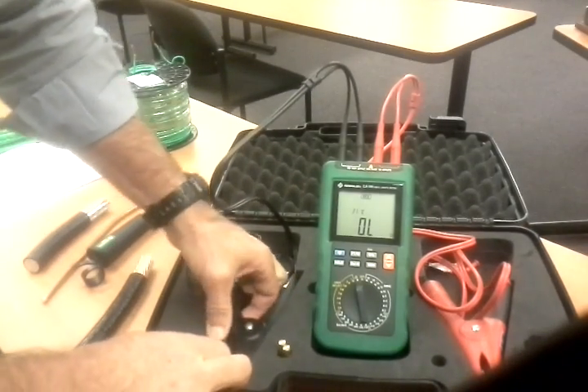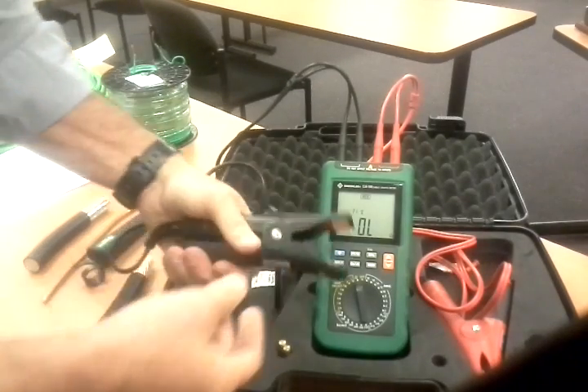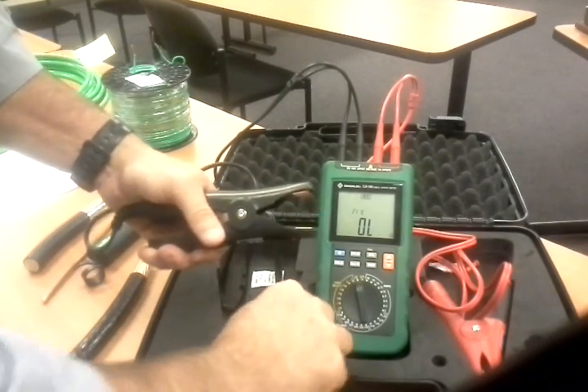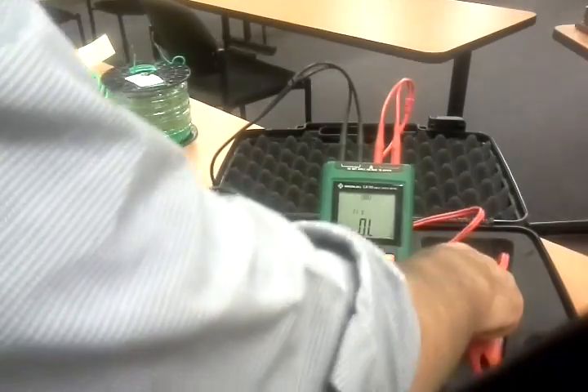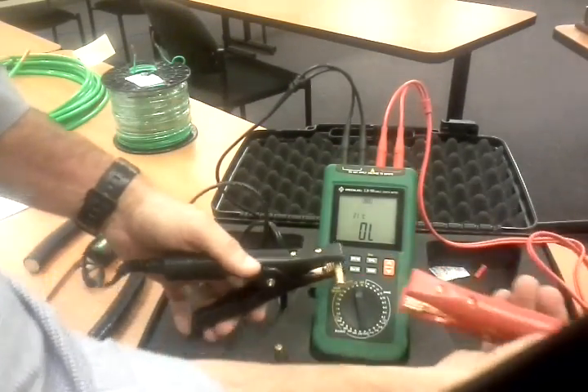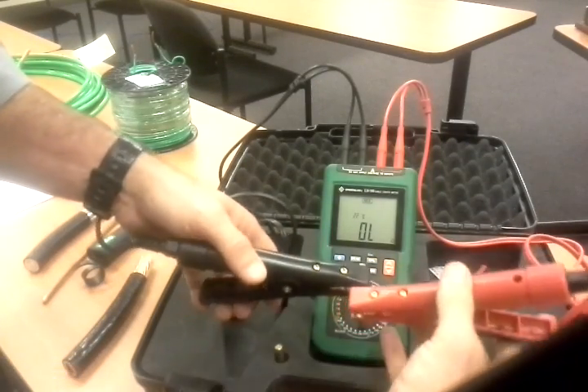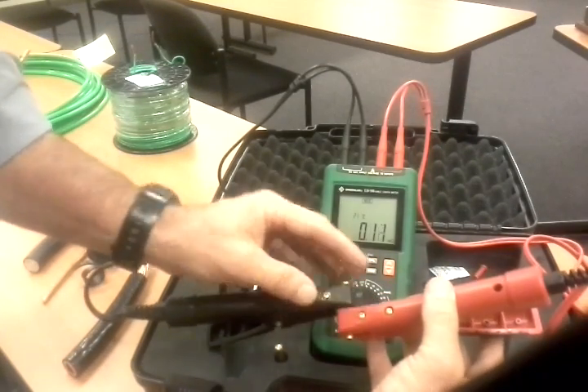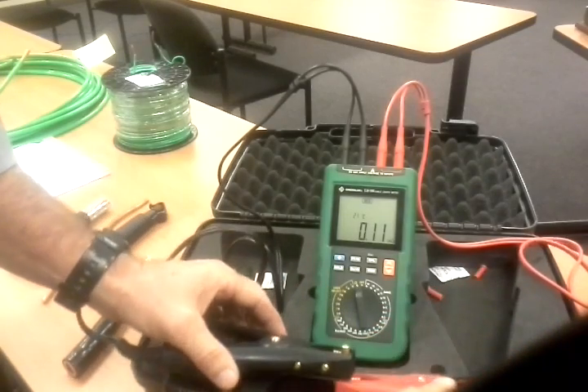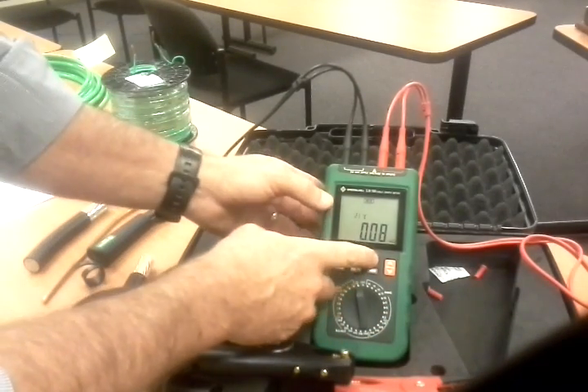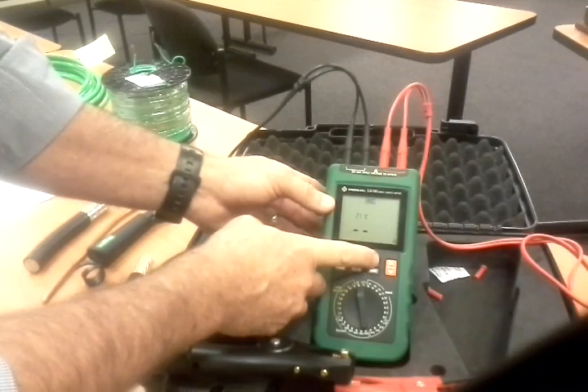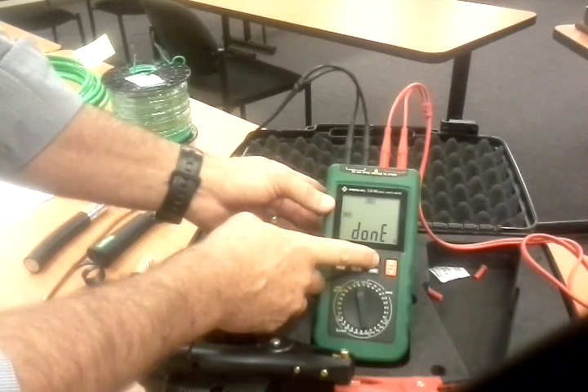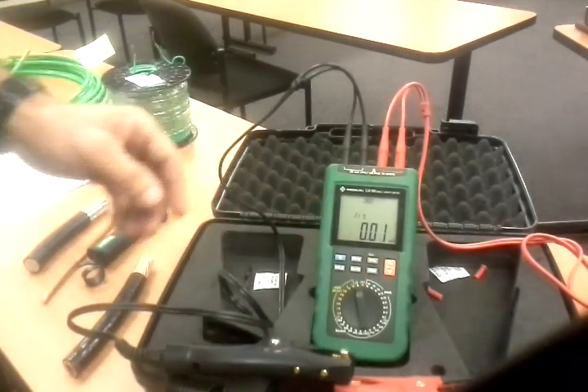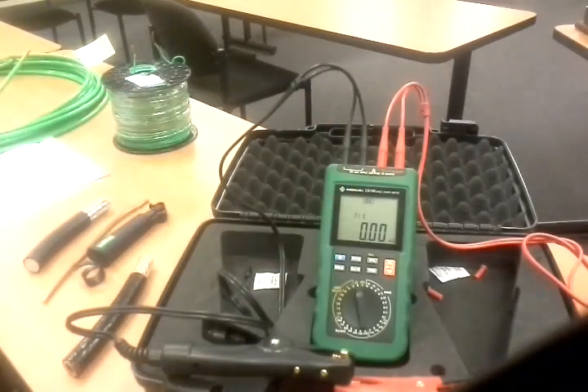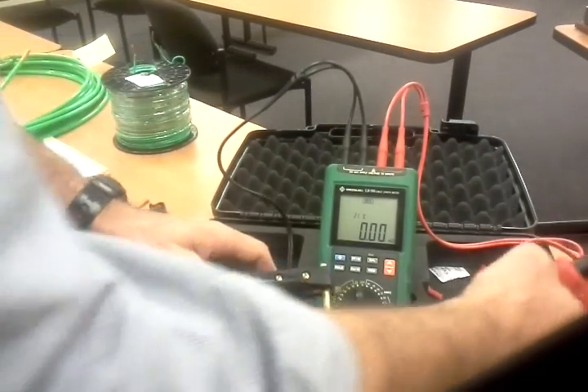Take your 2 leads. Make sure the leads themselves are clean of debris. Clip onto the calibration clip. Again, make sure your leads are clean. And then put the other lead on there as close as possible. You don't want them to be spread apart right here. Once you get those attached, you can press the calibration. You'll get 4 dashes that go across. Then the word done. And you'll see resistance at the top. It's ready to read. Go ahead and disconnect.